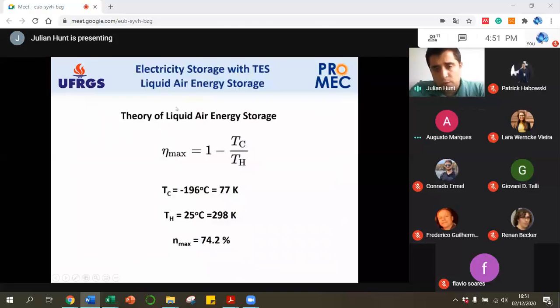But in this case, no one is going to cool down. There is no viable option for you to use a cold source in order to generate electricity. So liquid air energy storage is only used for electricity storage, it doesn't generate electricity. And given that the cold source is so cold, the cold source temperature divided by the hot temperature source is very small, which results in very high efficiency. So the thermal efficiency of this system is around 75%.